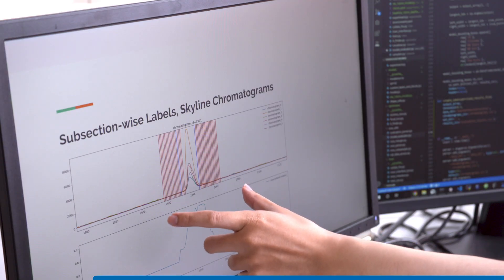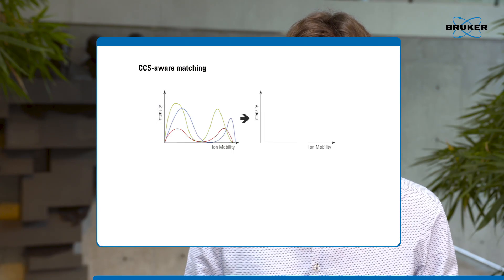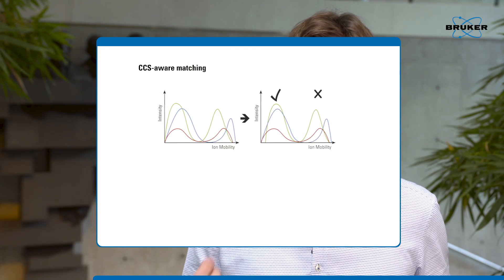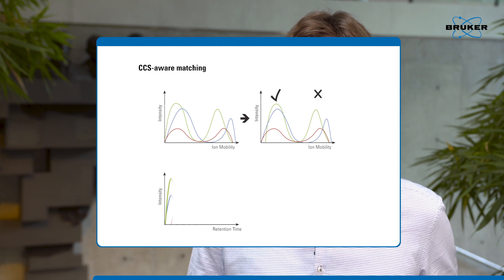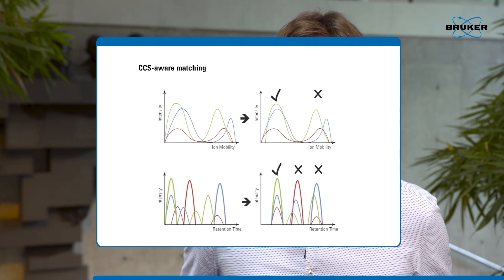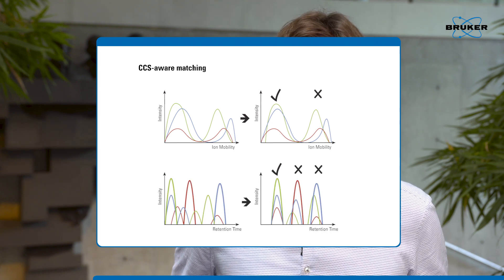When we use the TIMSTOF Pro to perform DIA-PASEF, it allows us to synchronize the quadrupole position with the elution in ion mobility, and this gives us a boost in throughput up to four-fold, getting four times as many ions into the detector, and this dramatically boosts the number of peptide identifications.